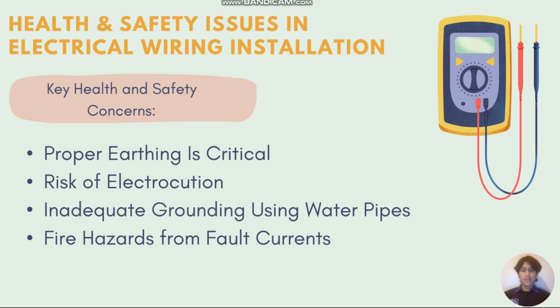For example, if the final circuit's metal clad is not connected to earth, any fault can cause exposed metal parts to become live, leading to possible electric shock to users and maintenance workers. And the third point is inadequate grounding using water pipes, which means water pipes connected to the public supply are unreliable grounding sources.